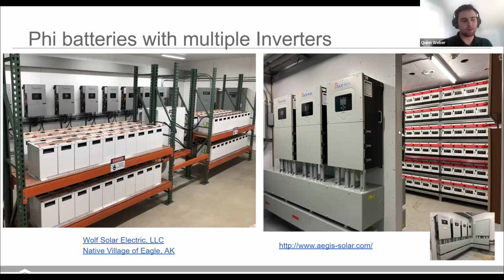If you're doing a Powerwall or a Franklin or an Enphase system, you have to pay for the additional inverter capacity that may not be needed. With Briggs & Stratton, you can easily add multiple batteries at any time. So major advantage between, yeah. Go ahead. I wanted to highlight that advantage. I mean, we unpacked a Franklin whole home, and that was my thought as well. One of the downsides to the Franklin is you've got a 507-pound installation, right? And it's all in one unit. And if you have a problem with the inverter, well, now you've got a problem with your battery. You have it all in one unit. You want to add storage? Well, now you've got to pay for all of those extra parts that you don't necessarily want.